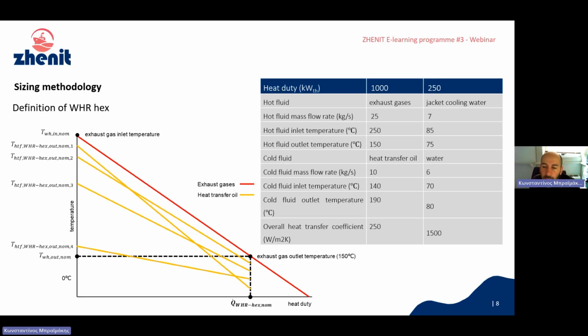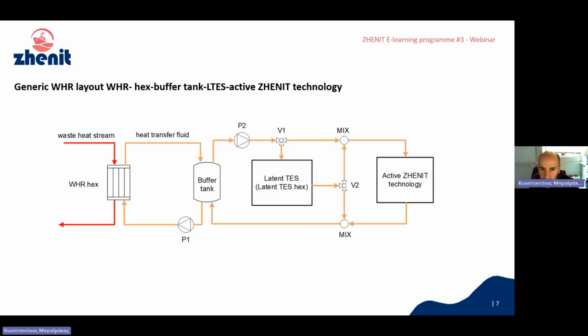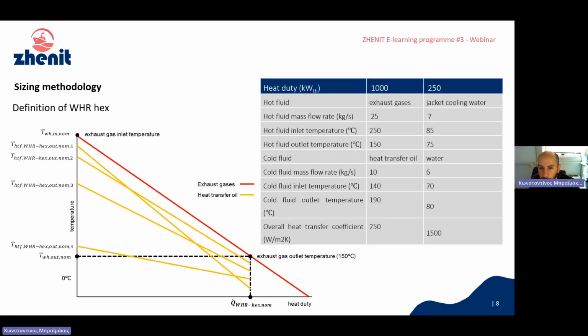So the first component to define is the waste heat recovery heat exchanger. This is this heat exchanger here. So for example, we have some specifications for this heat exchanger. In this case, we can have, for example, the exhaust gases, and we have this temperature profile of exhaust gases. And what we do is that we can assume a minimum exhaust gas temperature that is compatible with the chemical properties of the exhaust gases. And then we have several degrees of freedom regarding how to size the thermal oil or the heat recovery fluid, for example, the heat transfer oil that goes into this heat exchanger.